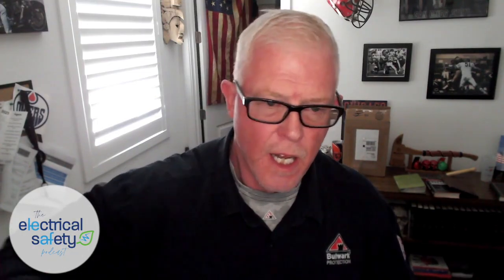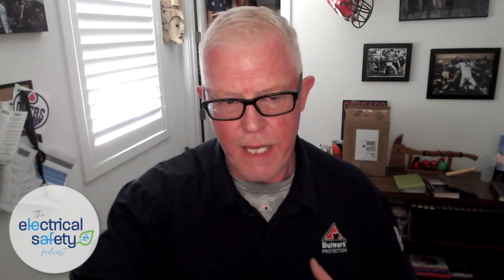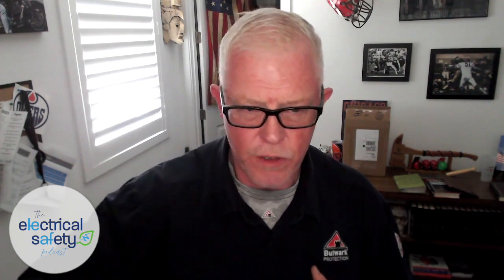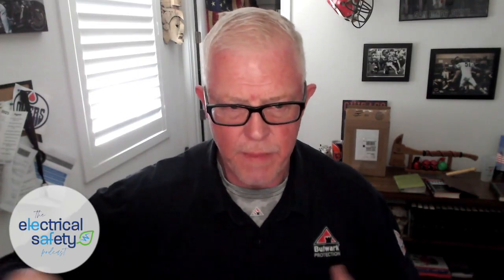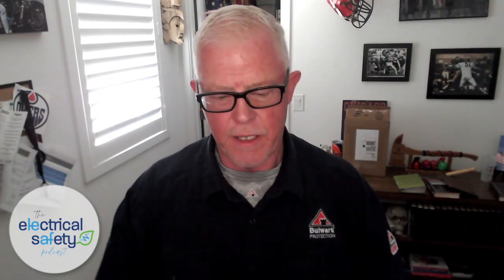Now, I don't want to categorically say, okay, let's go willy-nilly and start wearing 8 cal when that panel says 35. I want to still be wearing 8 cal when my panel says 7, and I just want to deal with those variables that I talked about, where I could take that 7 and push it to 18 or 20 based on distance and clearing time. I don't want anyone to think I can just wear my Cat 2 clothing in front of a Cat 4 panel. That's not what we're talking about. We're just talking about getting more exposure than what was labeled, based on those two variables influencing the incident energy.